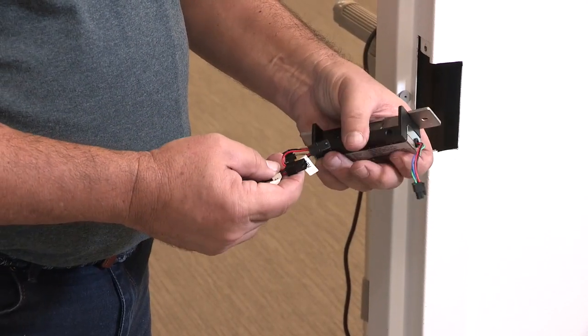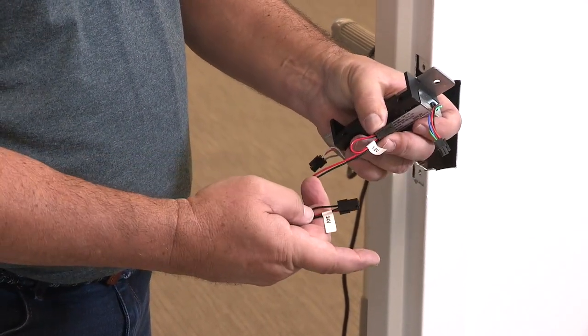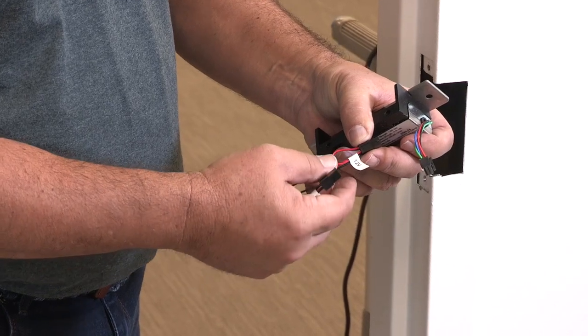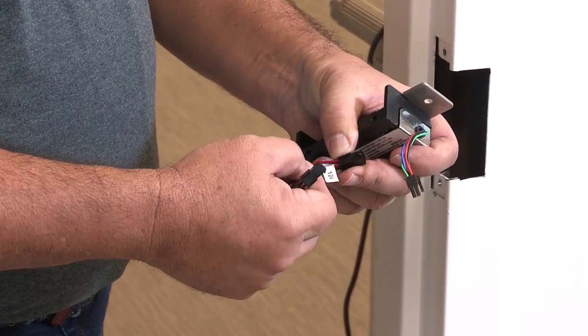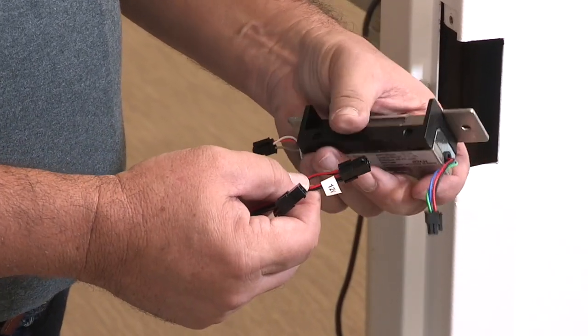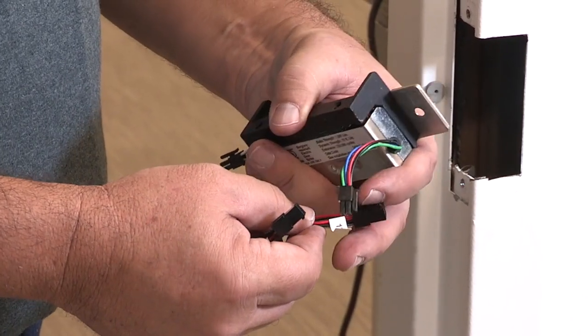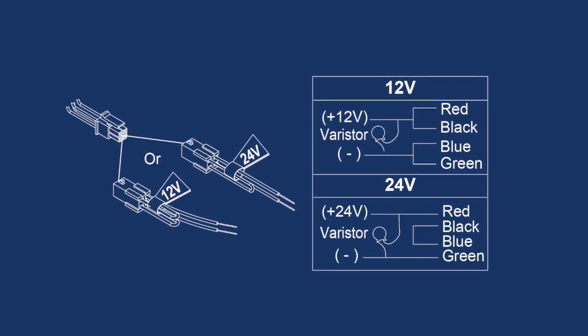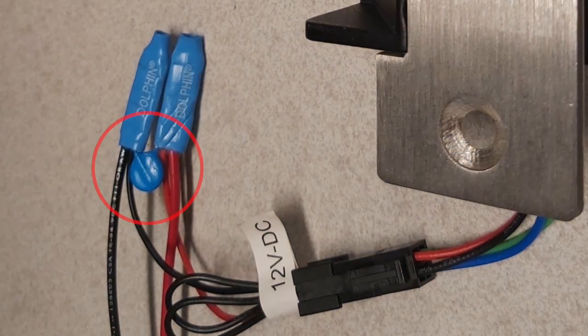12 or 24 volt power is selected using the correct black connector cable. This strike draws 260 milliamps at 12 volts DC. We recommend that the strike be on its own power circuit, and that you install an MOV varistor to prevent damage to the strike by power spikes.